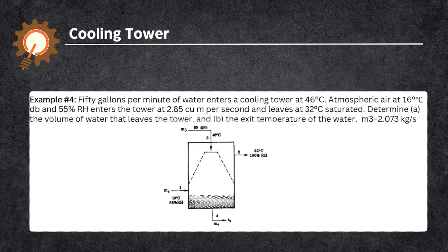Ang ating M3 ay equals to 2.073 kg per second. So, for point 1, kukuhanin natin yung H1 or enthalpy number 1, specific humidity number 1, at specific volume number 1 sa dry bulb temperature na 16 degrees Celsius at relative humidity na 55%. Ang H1 natin dyan ay equal sa 32 kilojoules per kilogram, ang ating SH1 ay equals sa 0.0056 kilograms per kilogram, at ang ating specific volume number 1 ay equals sa 0.828 cubic meter per kilogram.